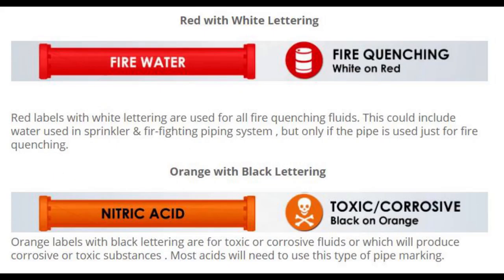Red with white lettering: Red labels with white lettering are used for all fire quenching fluids. This could include water used in sprinkler and fire fighting piping systems, but only if the pipe is used just for fire quenching.